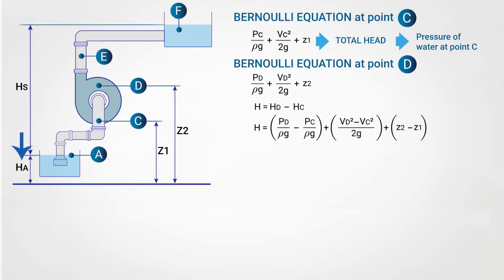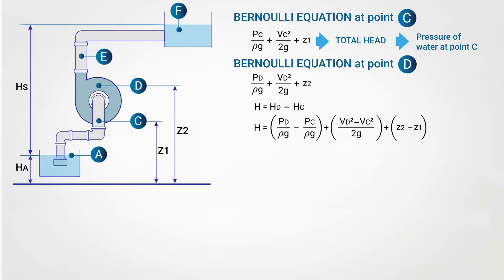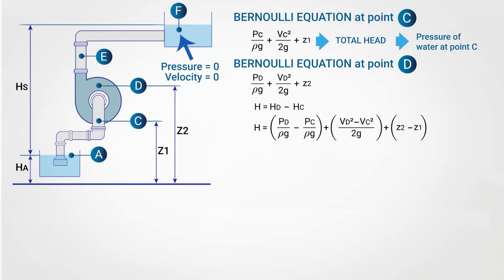The value HA represents the total head of water at point A. At this point the pressure head is zero because it is open to the atmosphere, and the velocity is also zero because the water is not moving. The distance between point A of the lower reservoir and point F of the upper reservoir is HS, known as the static head. At point F, the water is also open to the atmosphere so its pressure head is zero. The total height H in this case is HA plus HS.